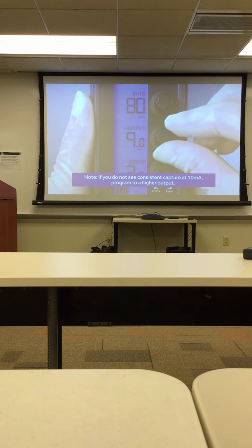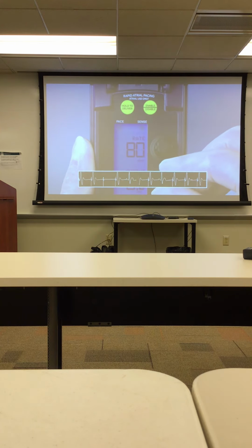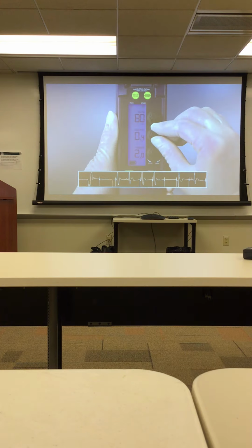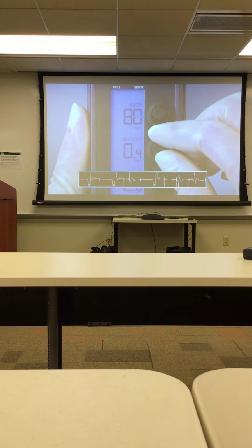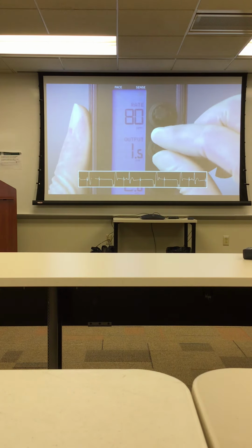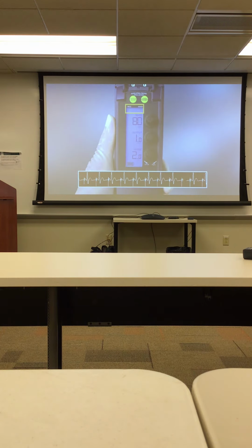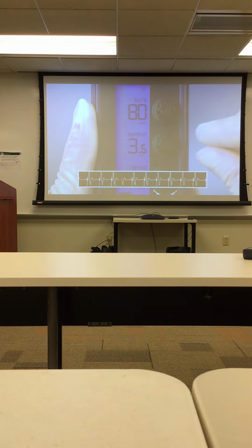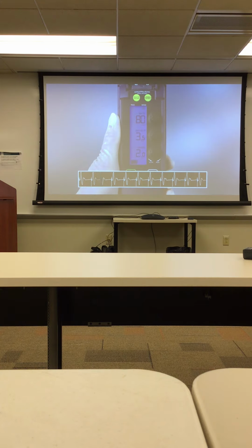Slowly decrease the milliamps by turning the output dial counterclockwise until the ECG shows loss of capture. Watch the pace and sense indicators to see if the device is sensing and pacing consistent with the ECG monitor. Next, slowly increase the milliamps until the ECG shows consistent capture. The pace indicator will flash continuously and the sense indicator will stop flashing. This is the stimulation or pacing threshold. Set the pacing output to a value at least 2 to 3 times greater than the pacing threshold value. Since the threshold is 1 milliamp, set the output at 2 to 3 milliamps.